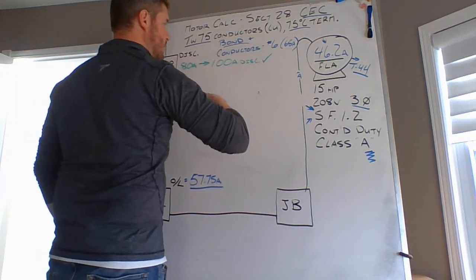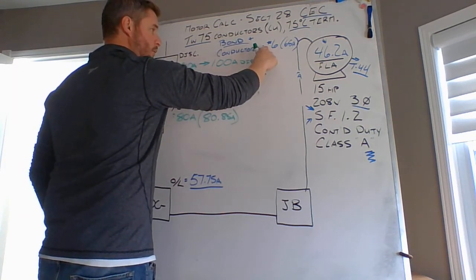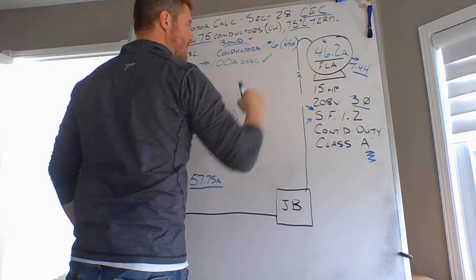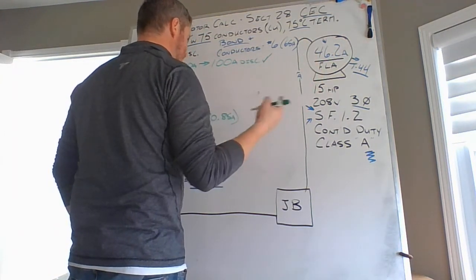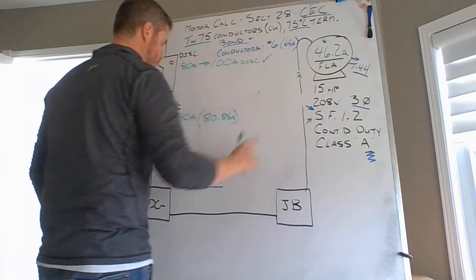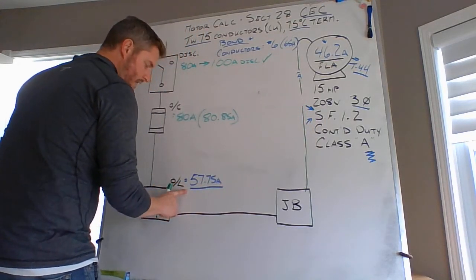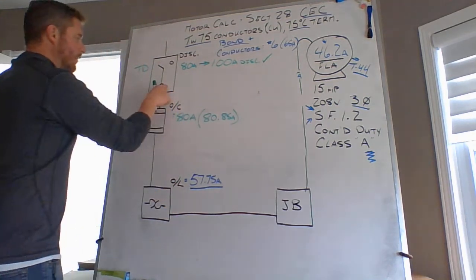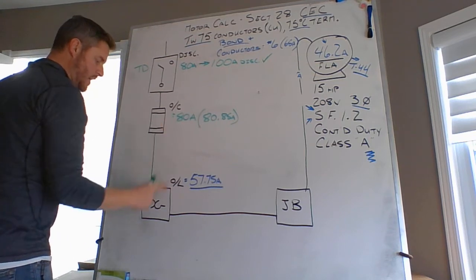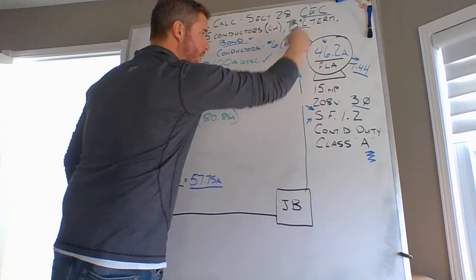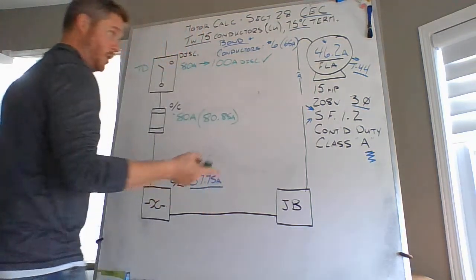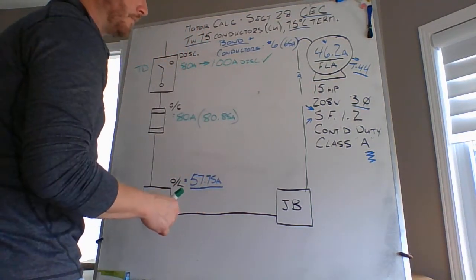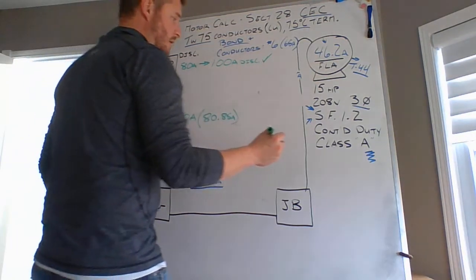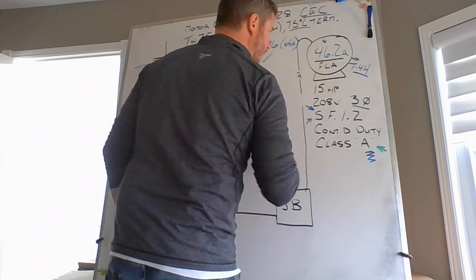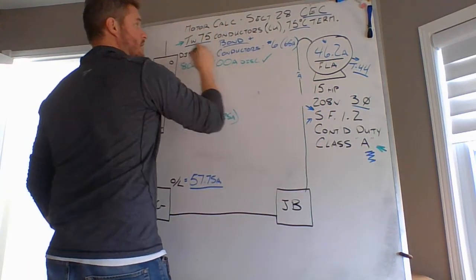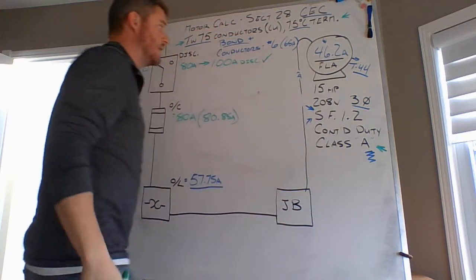So right now for this situation, you are going to install number 6 conductors, a red, a black, and a blue, going to feed a motor that is rated for 46.2 amps as a full load current rating with a service factor of 1.2, setting your overloads at 57.75 amps. From the load side of the disconnect, through your overcurrent device, into your overload, into this junction box and feeding your motor, which should never draw more than 46.2 amps, coming from table 44. Your installations are based on this class A, and we know that we're running TW75 conductors, and everything is terminated at 75 degrees Celsius.